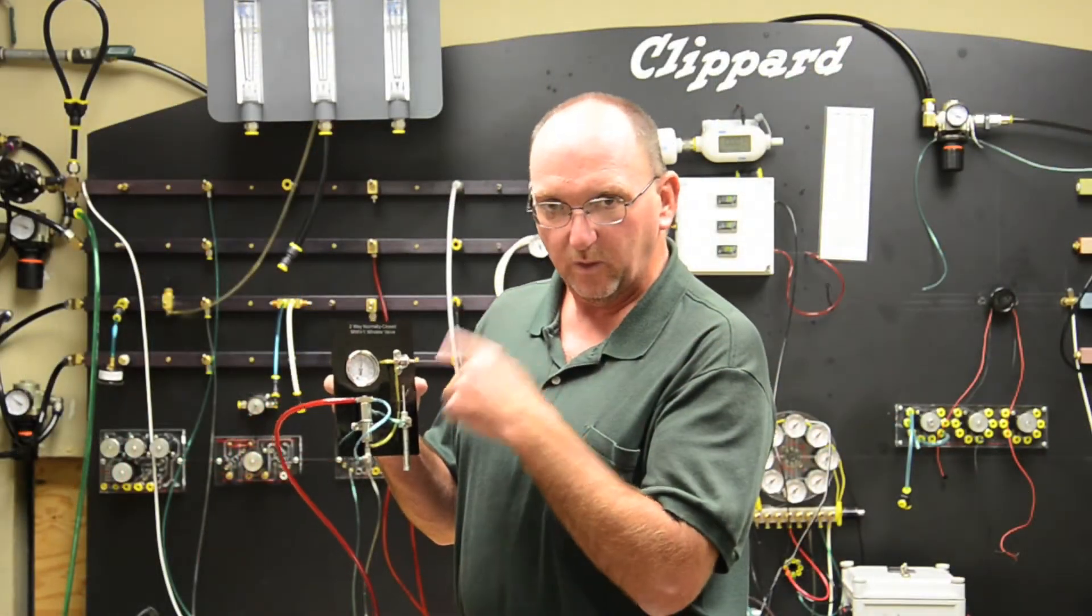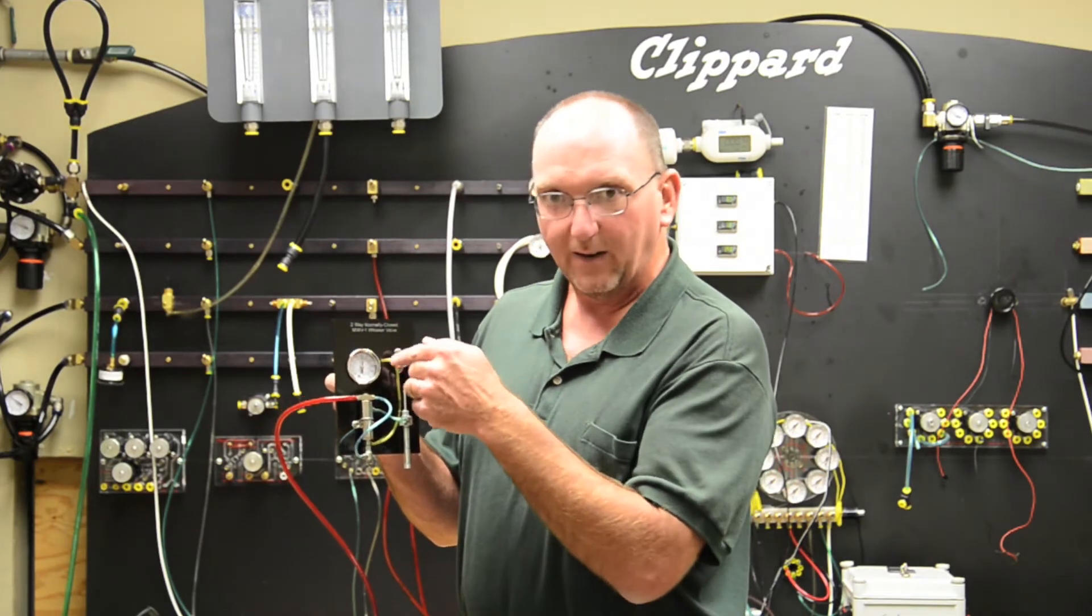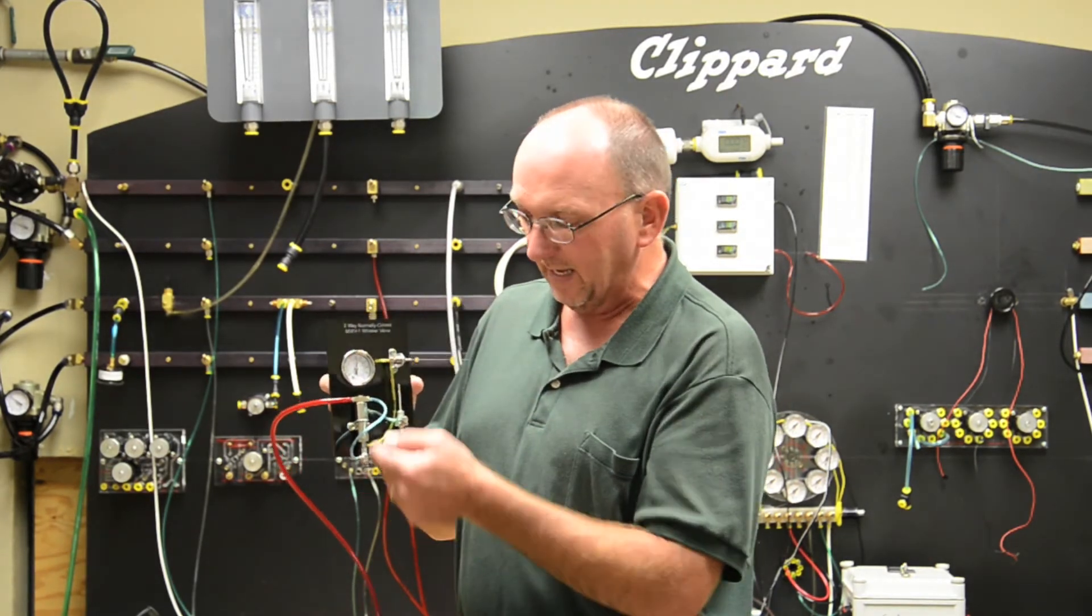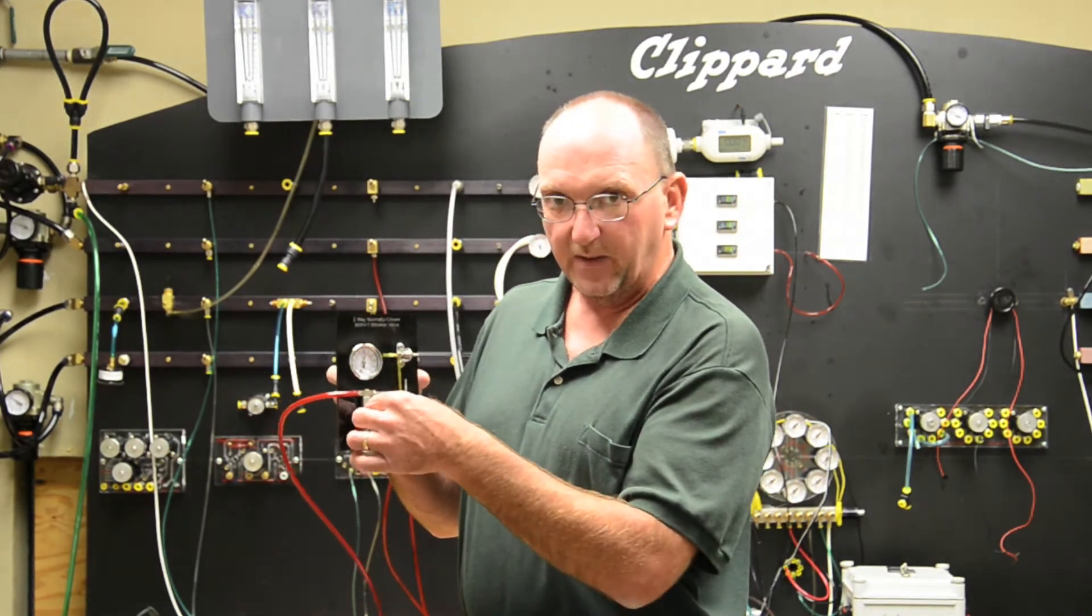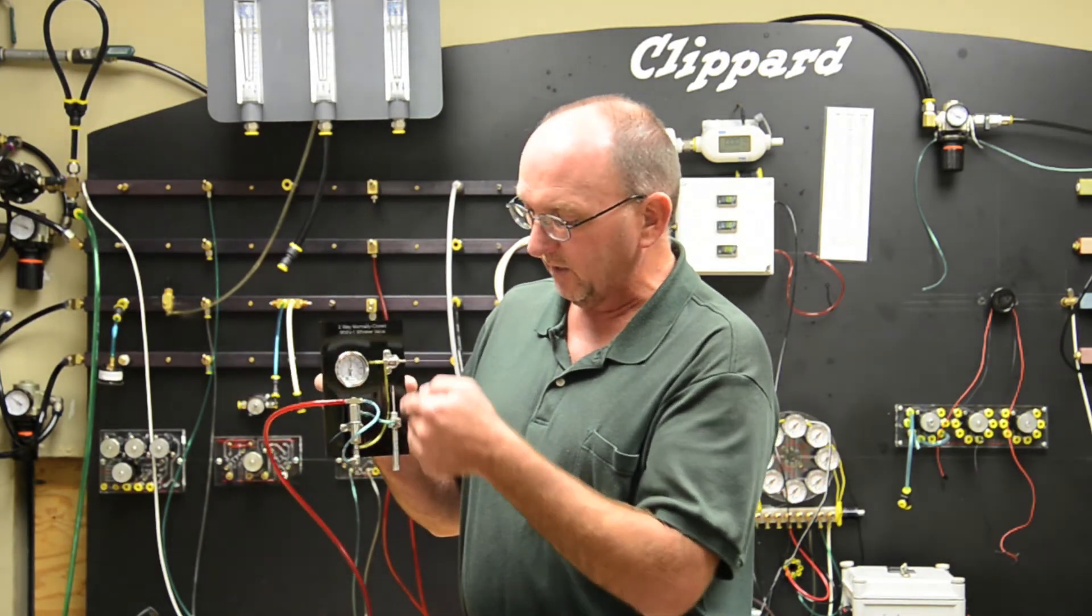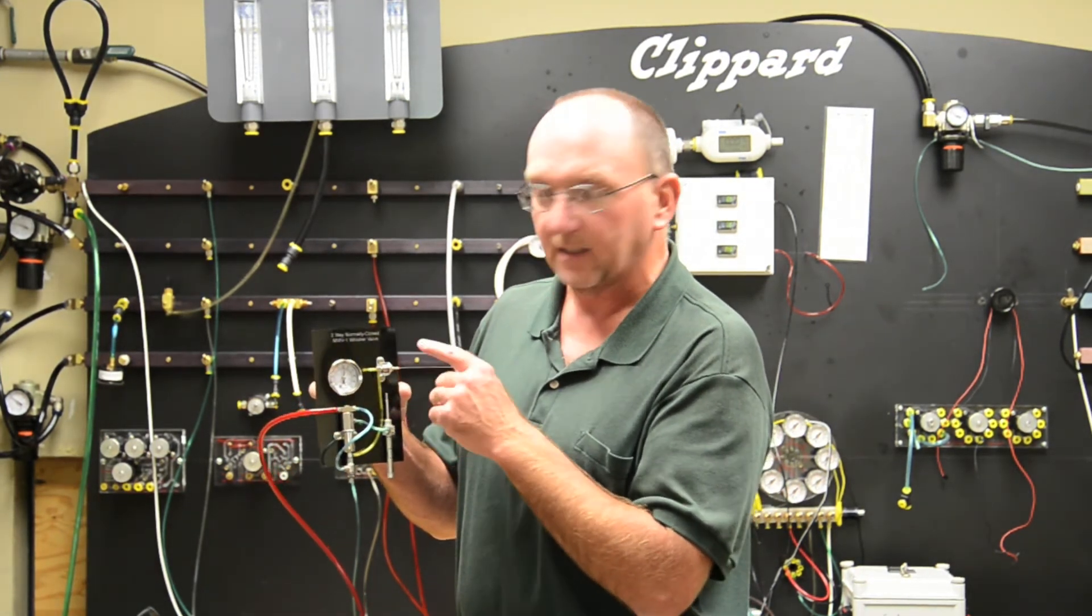And what occurs is when the whisker is deflected, more air escapes out the whisker than the needle allows to recover and the three-way valve springs to its open condition giving us an output to this single acting air cylinder.